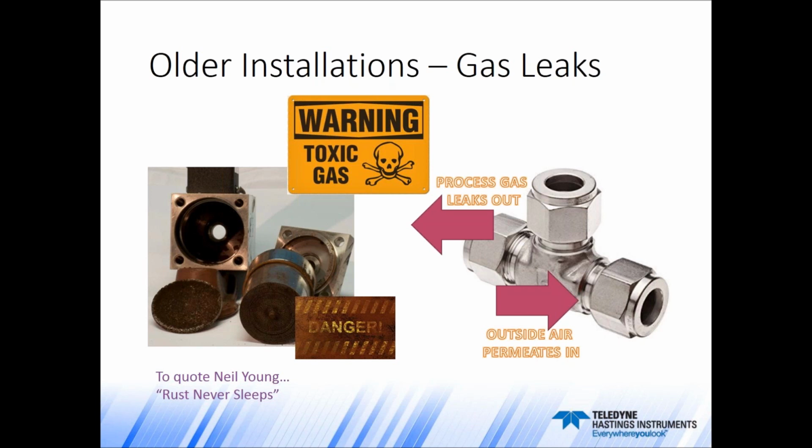One recommendation that we always make when we talk to our customers, if you have contaminated devices, and I will point you to the left of this slide where you see this incredible quote from Neil Young, "Rust never sleeps." Sometimes we see devices that are contaminated, removed from the line, and kept somewhere in a warehouse for a long period of time. What happens is corrosion will continue to affect these devices and that will totally destroy them eventually.